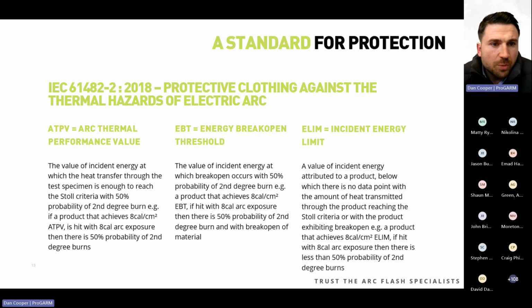Essentially, for the arc thermal performance value, if a product that achieves an 8 cal ATPV is hit with an 8 cal arc exposure, then there's a 50% probability of second degree burns. It's important to understand that there's still a 50% probability. This isn't always commonly known. When I have conversations, people assume that if you're wearing 8 cal, it's fully going to protect you from 8 cal. But under the ATPV and the EBT, there is that 50% probability of second degree burn, and with the EBT, that's also with break open of material.